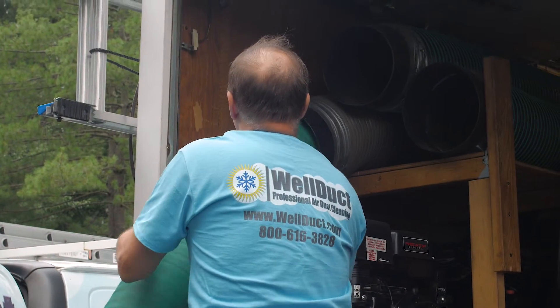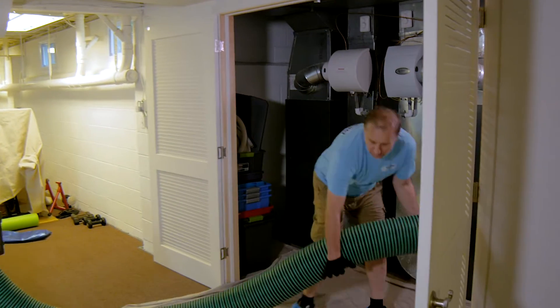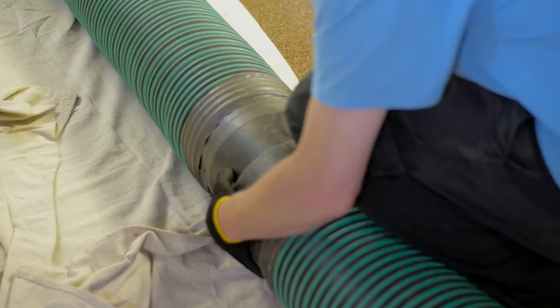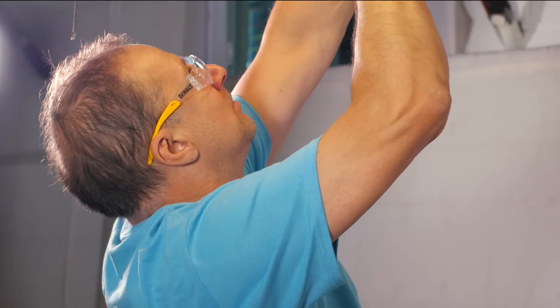The return is quite large and normally more contaminated, so we're using a 7,000 cubic feet per minute gasoline powered vacuum in order to depressurize it. For cleaning the supply air ducts, we're using a 5,000 cubic feet per minute electric negative air machine with true HEPA filtration.